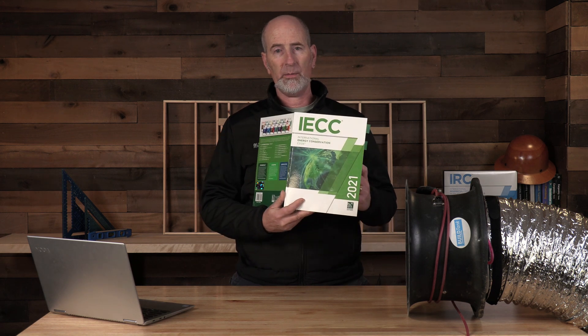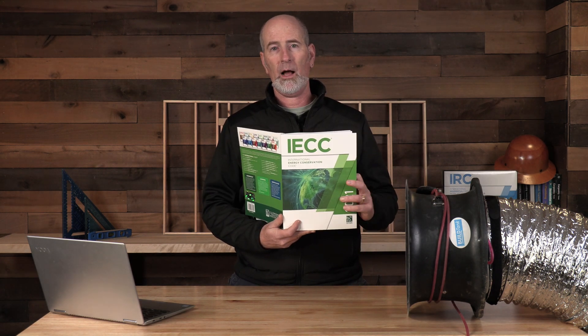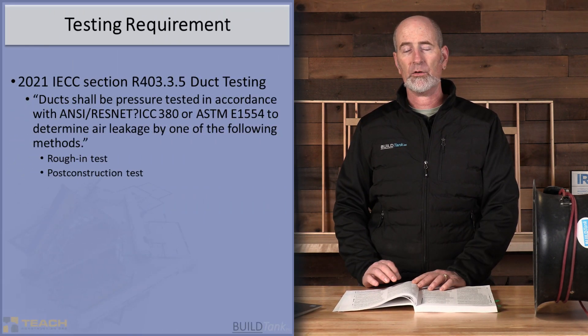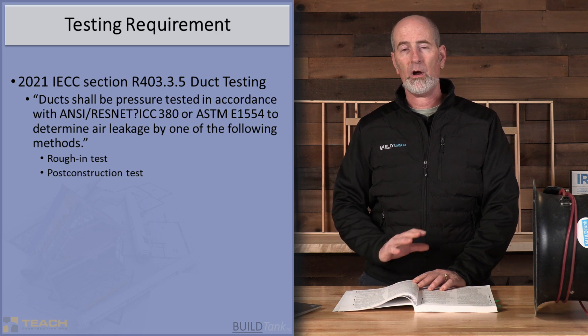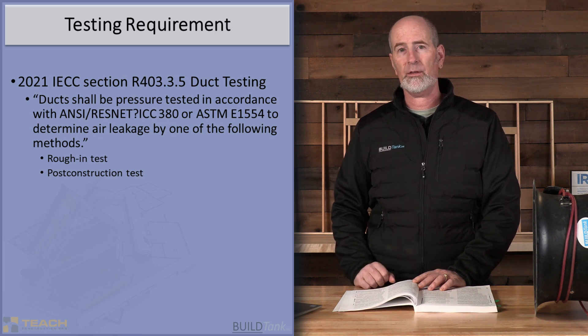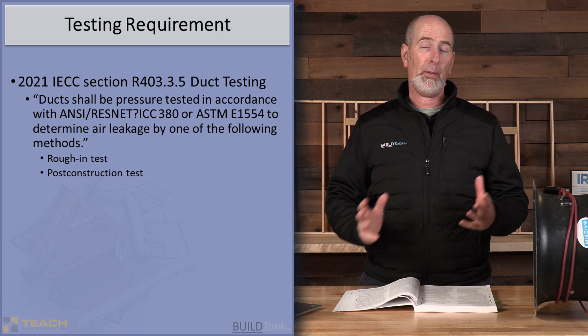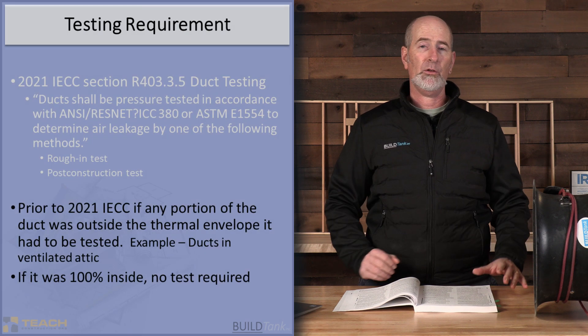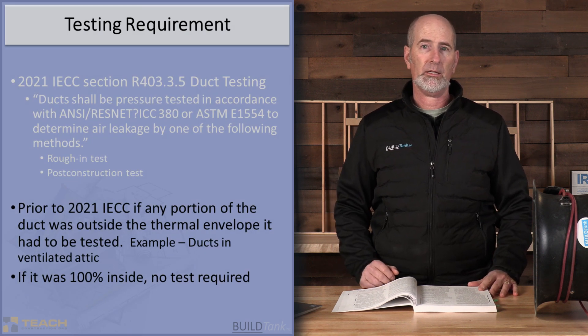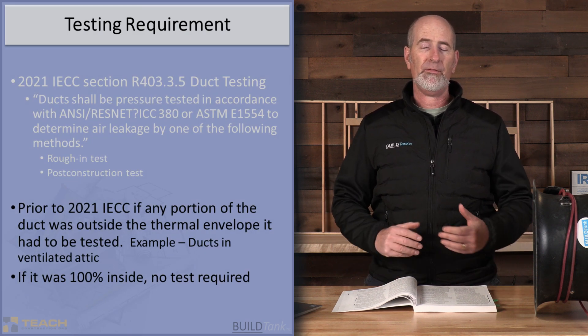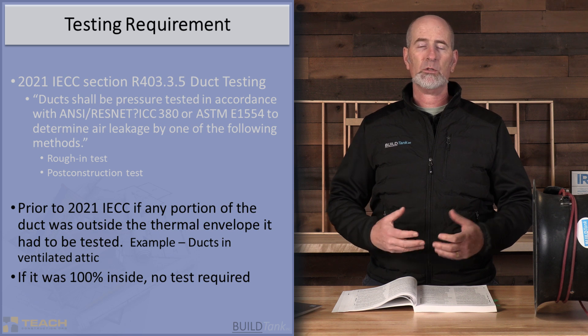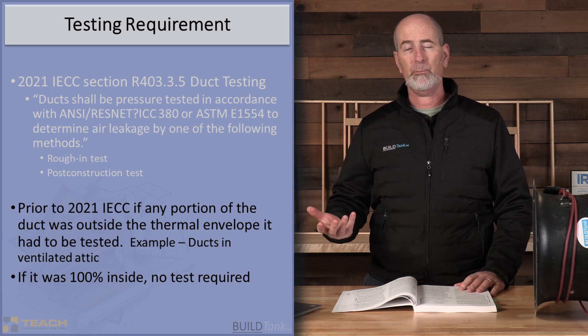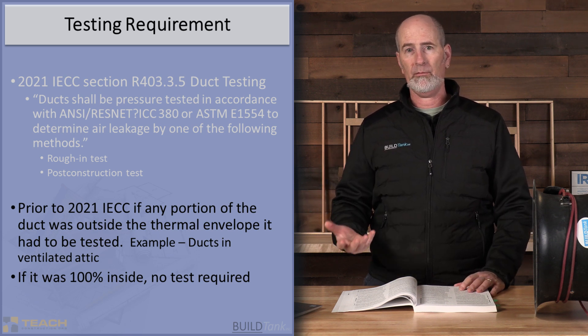Specifically, we're going to be talking about the 2021 IECC because new to the 2021 IECC is a requirement to test for total duct leakage regardless of where the ducts are located. In the past, you only had to test for total duct leakage if any portion of that duct was located outside the building thermal envelope.